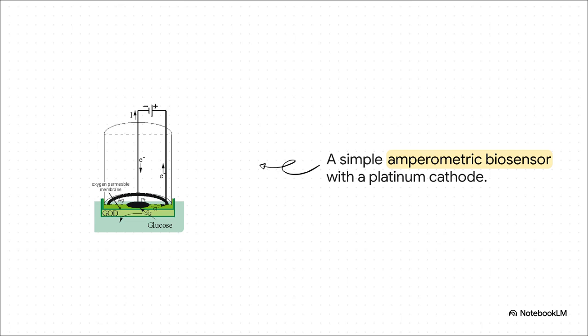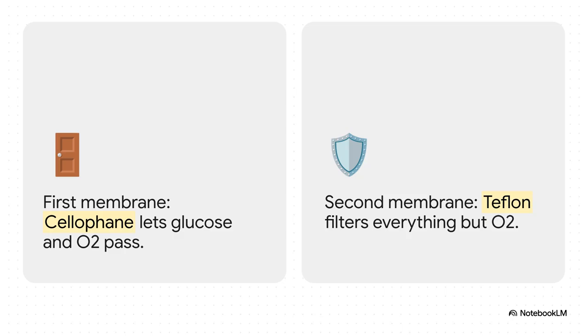But the true, absolute secret to making this device actually function reliably in a complex, messy biological fluid like blood, that came down to its protective barriers. The sheer genius of the device lies in its dual membrane system. It separates the messy biological sample from the super-sensitive electrode reading the remaining oxygen.